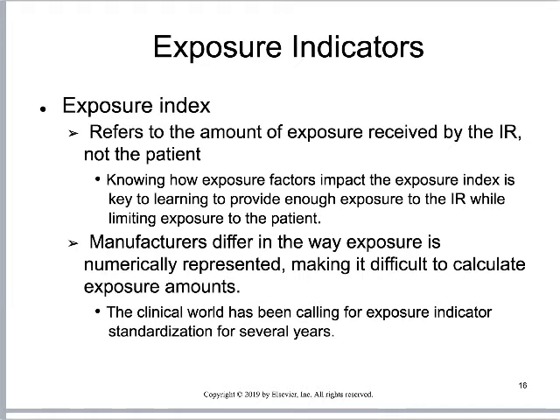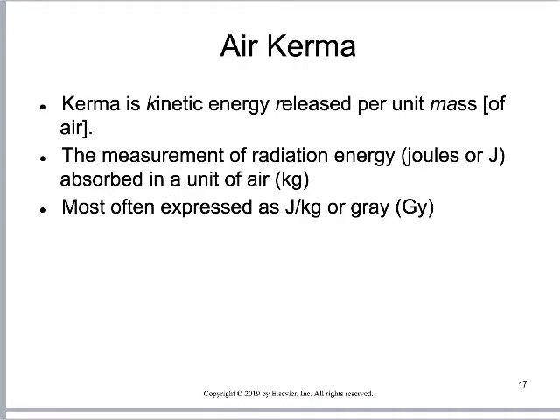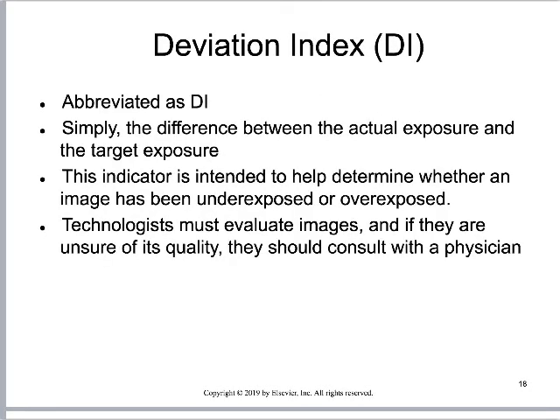Manufacturers differ in how exposure is numerically represented, and we've been asking for a clinical standard exposure indicator for a long time without one yet. We are working towards something called a deviation index, which will help us have a standardized exposure indicator. To understand the deviation index, we first need to talk about air KERMA — kinetic energy released per unit mass of air. This measures the amount of radiation energy or work done in a volume of air, often expressed as joules per kilogram or simply the unit gray. We use KERMA to track the actual exposure at the image receptor versus what we expected, calculating the deviation index — how much the actual exposure differed from the expected exposure.